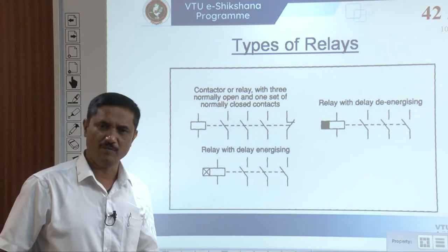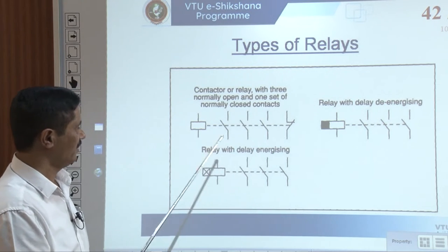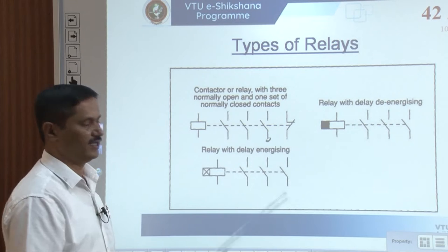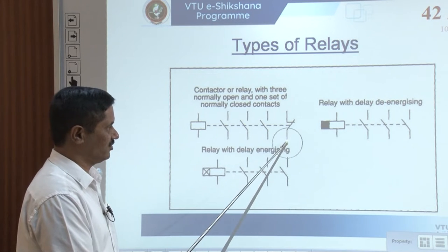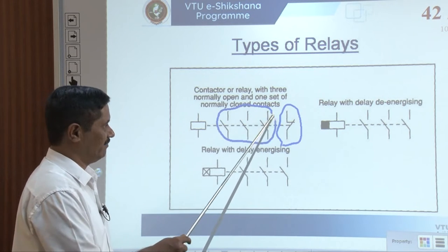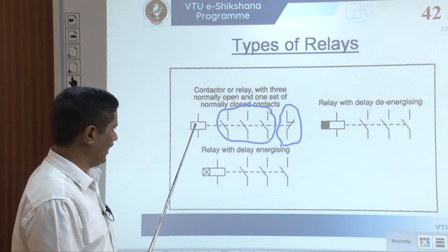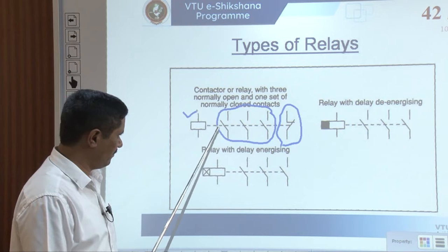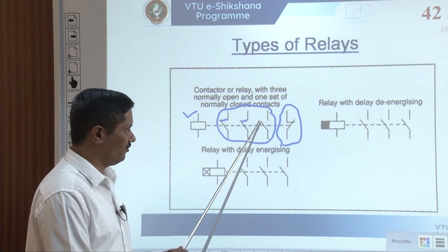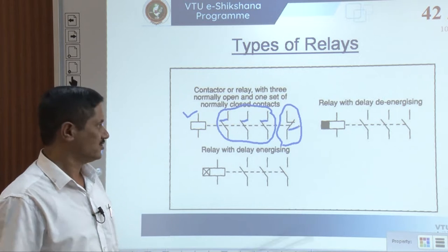Types of relays include a contactor with three normally open and one normally closed contact. When the relay coil gets energized, the electromagnetic force pulls the rod, so all NO contacts become NC and the previously NC contact becomes NO — meaning all three NO get closed and the NC opens. This allows you to enable three outputs to get on and break one output when the relay is energized.